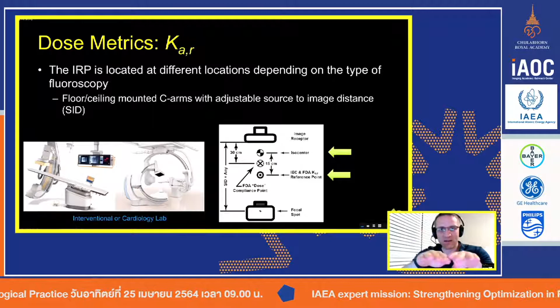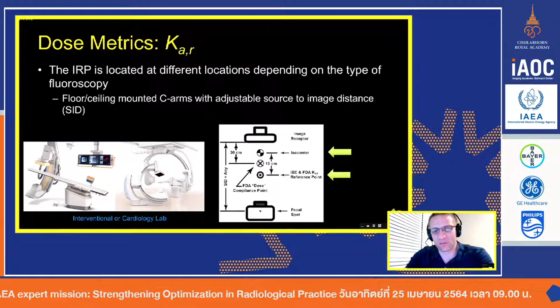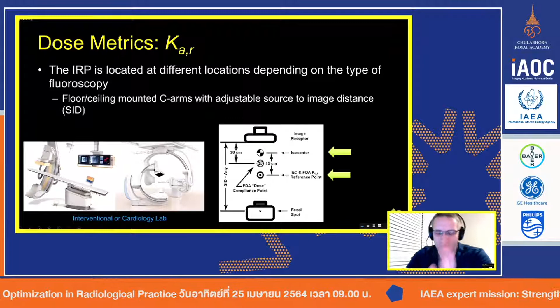Well, the reason for that is if you place that isocenter dead center to your patient, and we assume an average 30 centimeter anterior posterior depth, or thickness, of a patient, then if isocenter is at center, there would be 15 centimeters from the center to the entrance skin, or the patient's back, if they're laying supine on the table. That is why it's 15 centimeters. It approximates the point where the patient entrance skin dose would be calculated if they were a typical or average person laying supine or prone, I guess, doesn't matter, on the fluoro table.